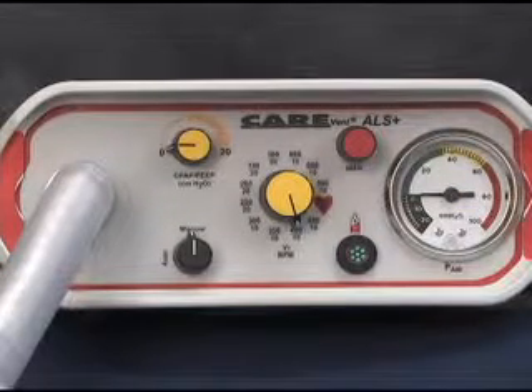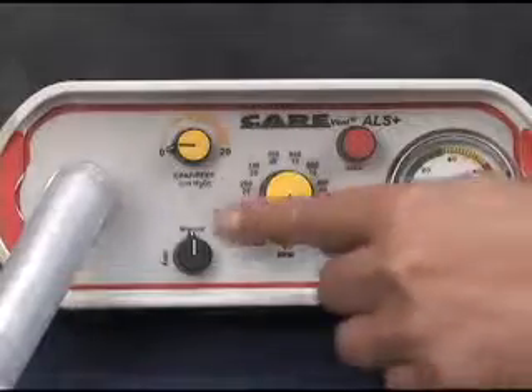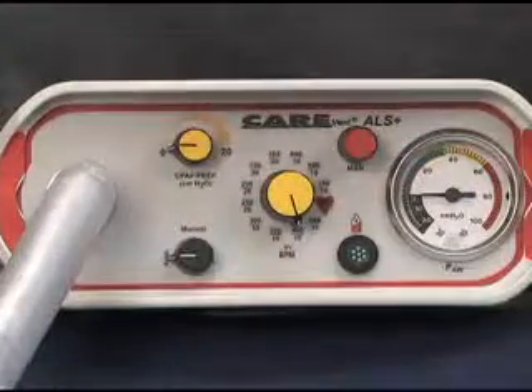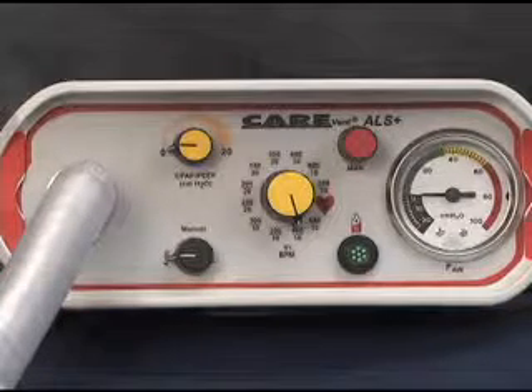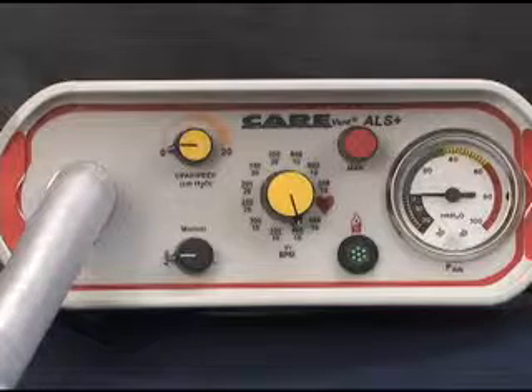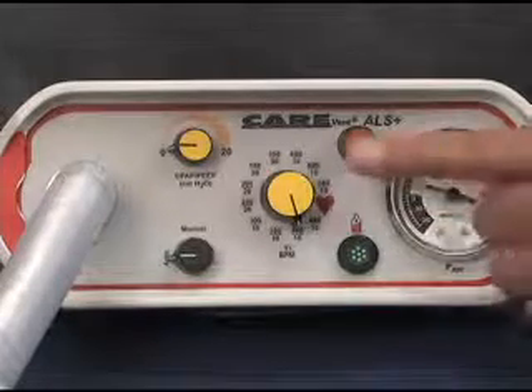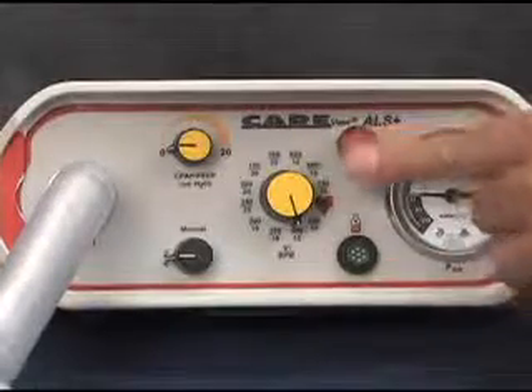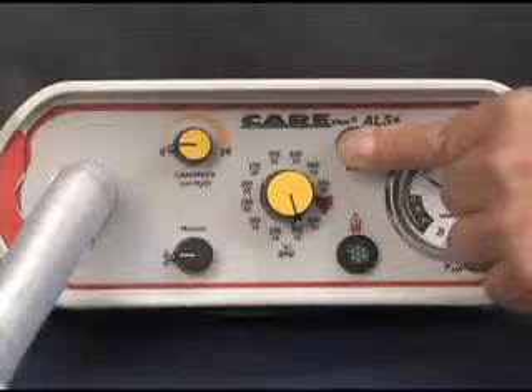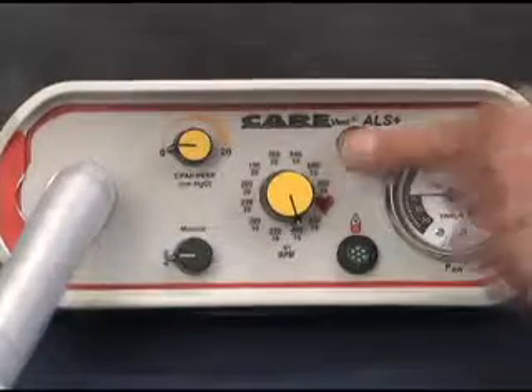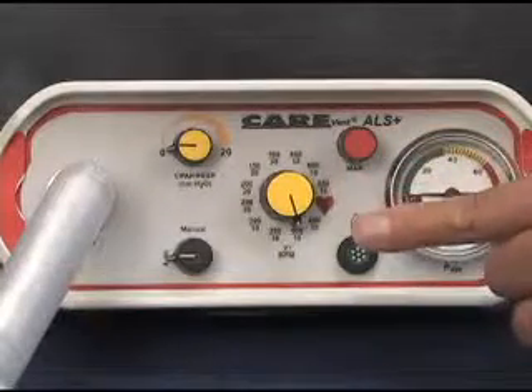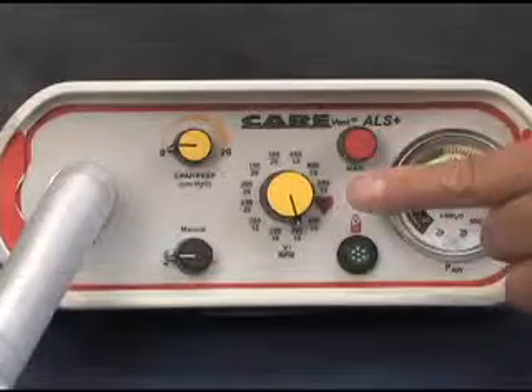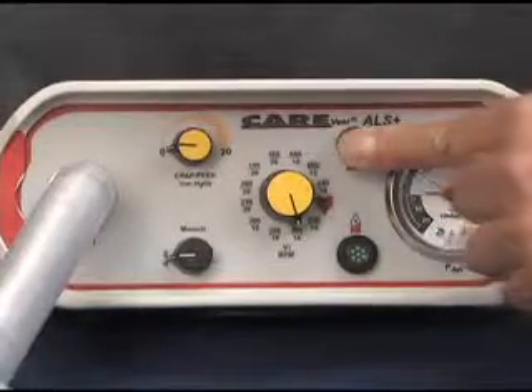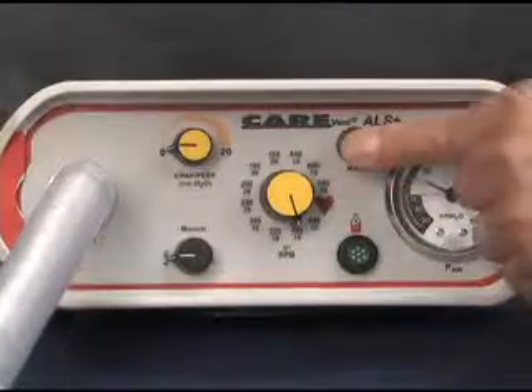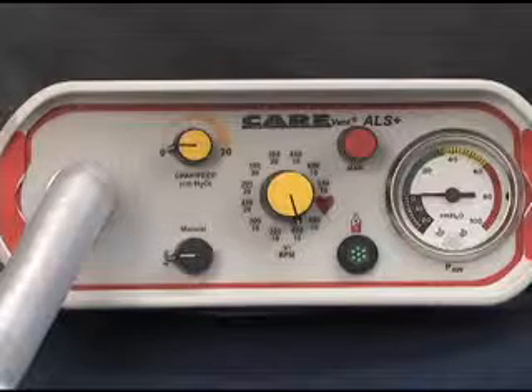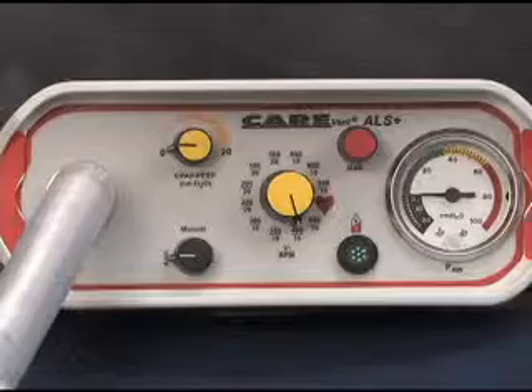With the manual auto control in the auto position, the CAREvent ALS Plus or ALS Plus CPAP will provide automatic ventilations at the rate and volume selected on the rotary setting selector control. At any time during automatic ventilation, the operator may override the automatic cycling by depressing the manual ventilation override button. This will cause the automatic cycling to cease to enable the provision of chest compressions in line with the current resuscitation guidelines. It can also be used to provide assisted ventilation to the spontaneously breathing patient. The manual gas flow is equivalent to the setting selected on the rotary setting selector control. If the rescuer fails to continue to actuate the manual ventilation override button, the ventilator will recommence automatic ventilations at the preset rate and volume.